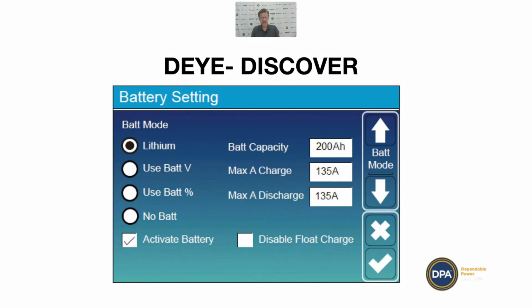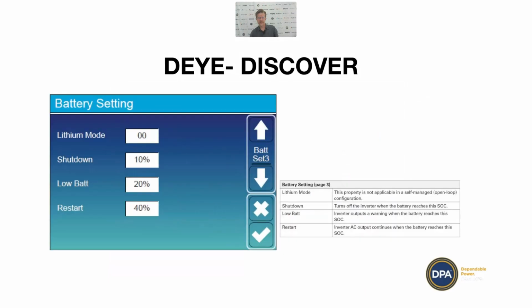But obviously adjust that according to how many batteries you've got, if that's the case. We want to have activate battery ticked, and we want to have disable float charge ticked. And then you're going to see this on page 3, and it's going to say lithium mode. You can't change that. And then you're going to set your shutdown, low battery and restart values here.